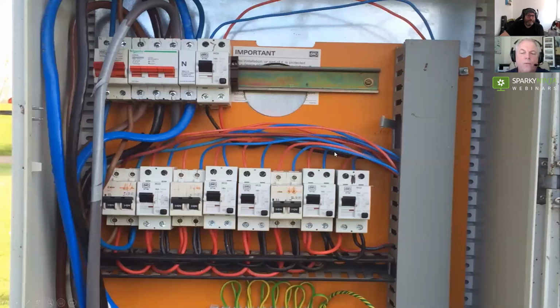What do you think? Well, my issue with this would be, you've got those big, large cables coming in, feeding in the top of that. Is that a circuit breaker? Or is that a switch disconnector? I can't really see from the... What, this big thing here? The big 3-phase one. That's just a switch disconnector, isn't it? I think it's just a switch. Yeah, I don't think it's actually got overcurrent protection. So there's no overcurrent protection going into that or coming through that.